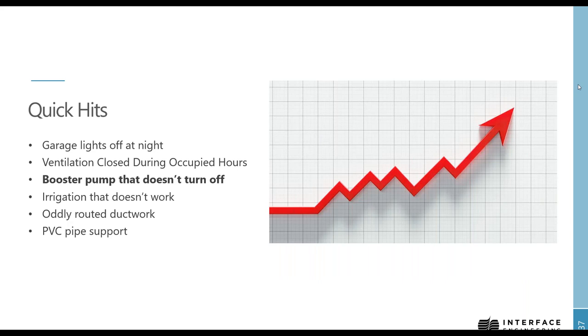The next item that we have here is something as simple as a booster pump. This is just bringing city water and giving it an extra push so that it can actually go up into the high-rise buildings or into spaces that just need the extra pressure. In this case, one of the examples that we saw was an incorrect set point during the initial startup resulted in a booster pump that would just run continuously. The obvious issue here is the energy costs, and that now you have a pump that's running 24/7 instead of really only running about 10 to 15% of the time under a typical operation.